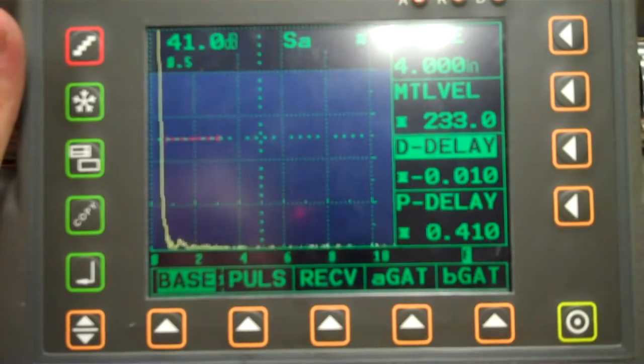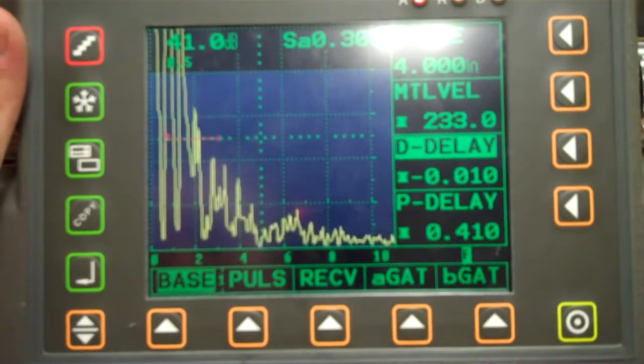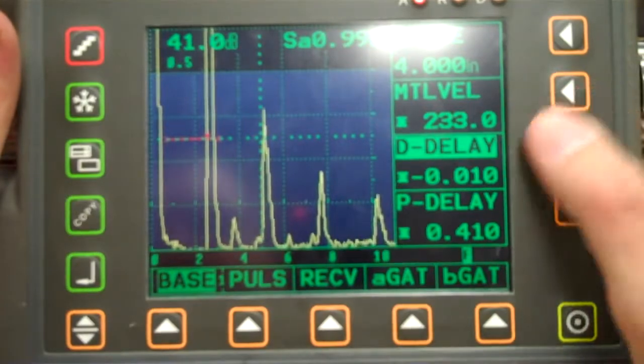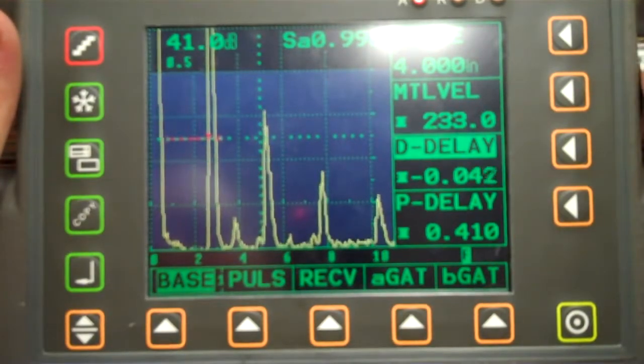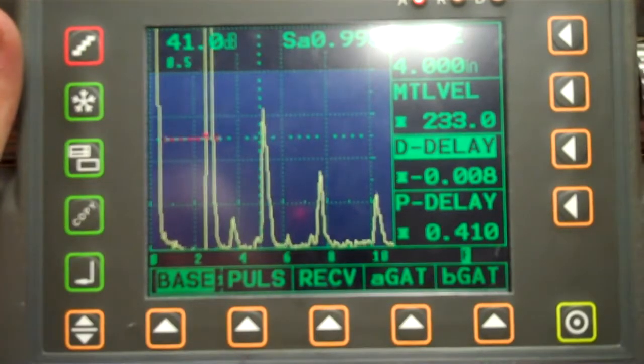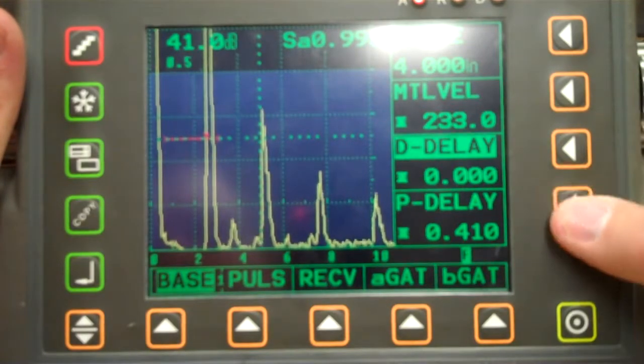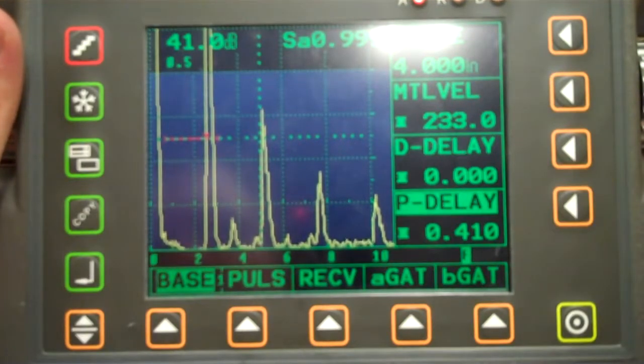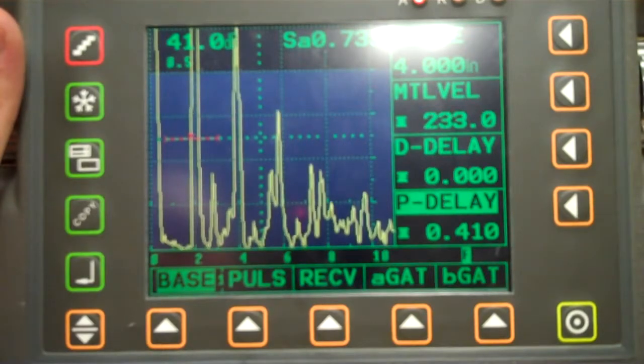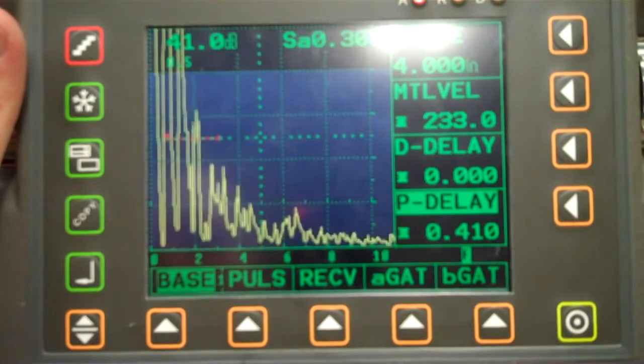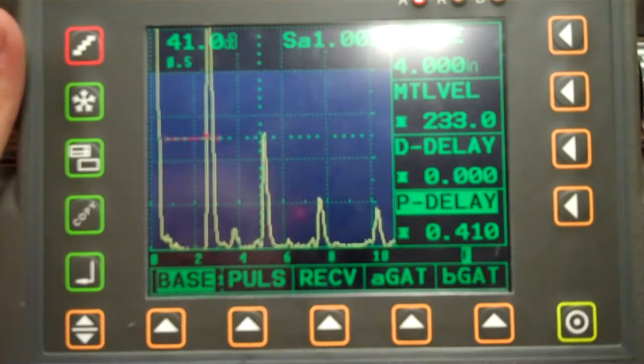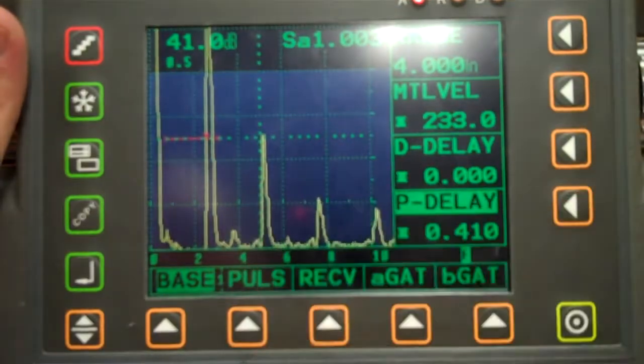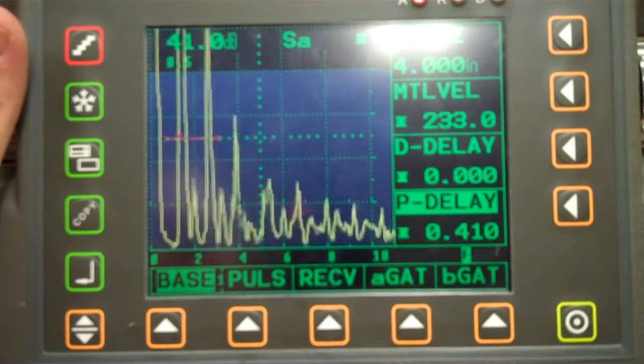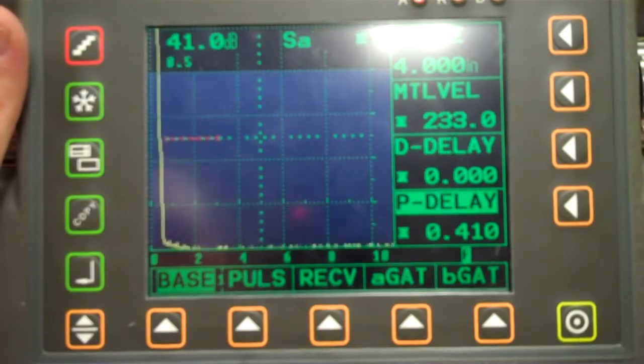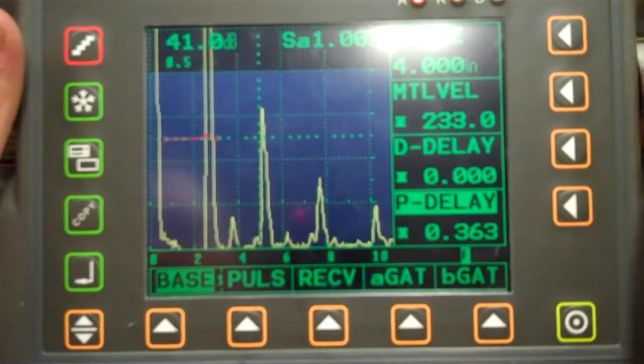3/4. I'm getting a little bit farther off all the time, which is okay, and that just means that I'm not calibrated where I need to be. So what I need to do is take this back all the way to 0. Going the wrong direction. Take that all the way to 0. And that brings me back to where I should be. Okay, so there's 1 inch. 3/4 I'm still off. Still off. Still off. Alright. So that means I'm good with the 1 inch. 1/2 inch is not so good. And 1/4 inch is not so good. So I would just take and continue to mess with this.